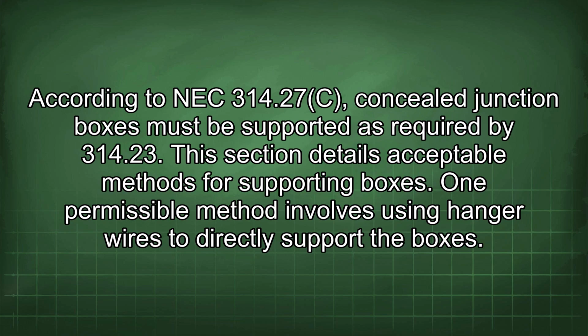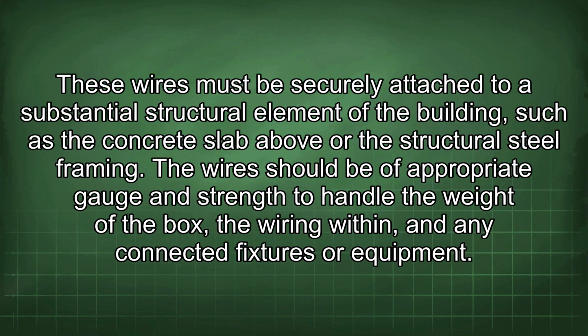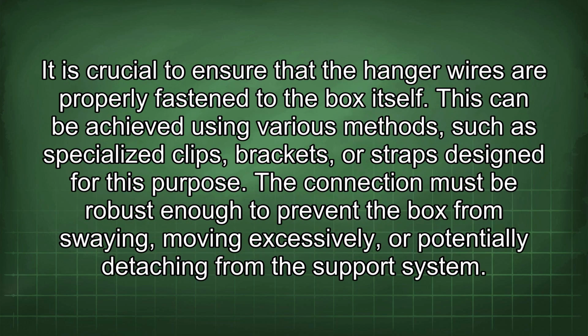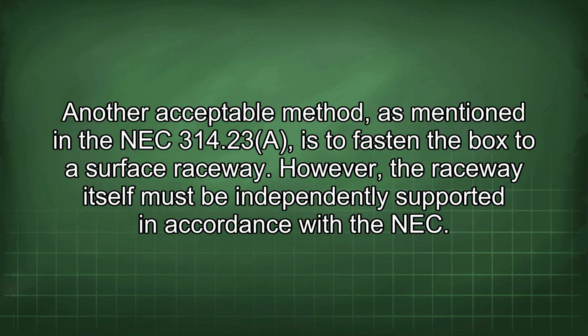One permissible method involves using hanger wires to directly support the boxes. These wires must be securely attached to a substantial structural element of the building, such as the concrete slab above or the structural steel framing. The wires should be of appropriate gauge and strength to handle the weight of the box, the wiring within, and any connected fixtures or equipment. It is crucial to ensure that the hanger wires are properly fastened to the box itself. This can be achieved using various methods, such as specialized clips, brackets, or straps designed for this purpose. The connection must be robust enough to prevent the box from swaying, moving excessively, or potentially detaching from the support system.